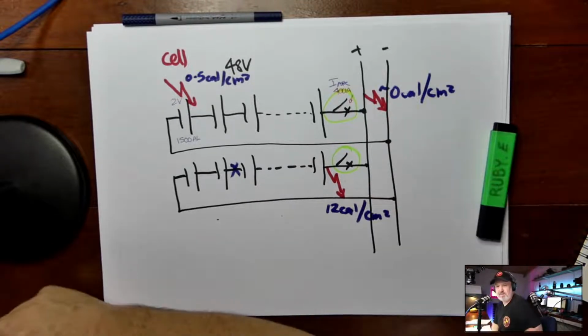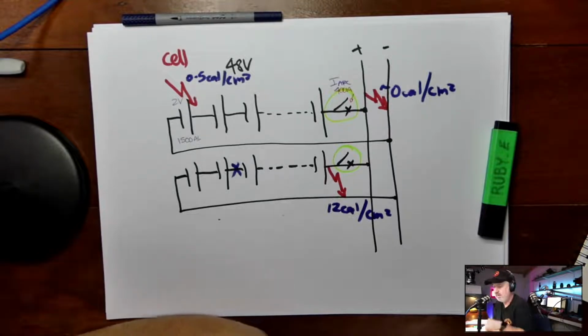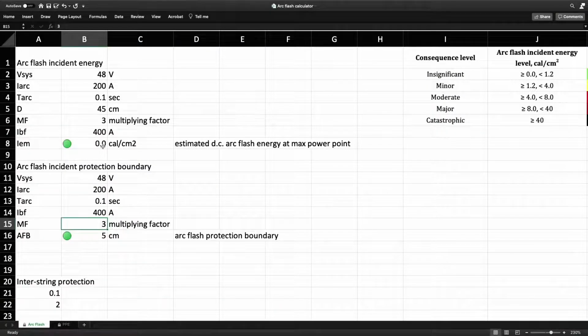Okay, so that's a basic design of a... hang on, go back to my right picture. That's a basic design of a battery system. It's a very big one. It was an off-grid system, 2 strings of 1500 amp hour cells, but we worked through the design in terms of protection, cable sizing, distance of the isolator from the battery system and from the PCE.